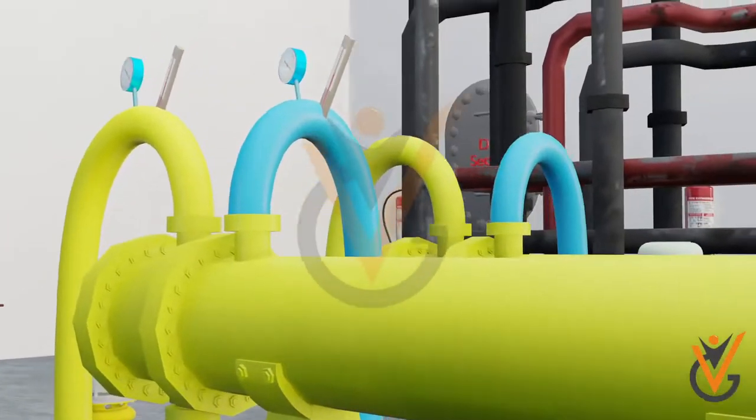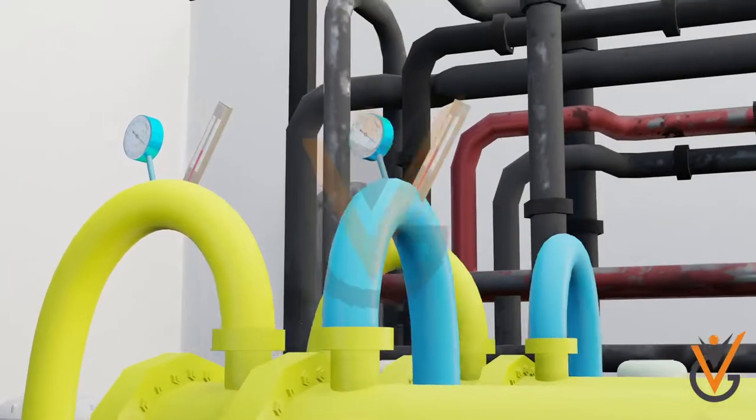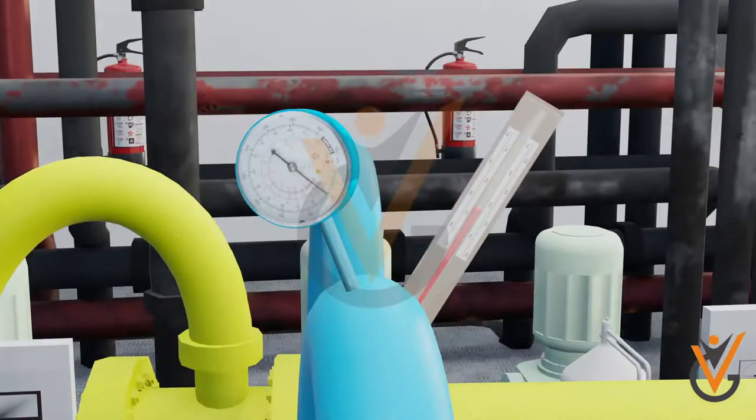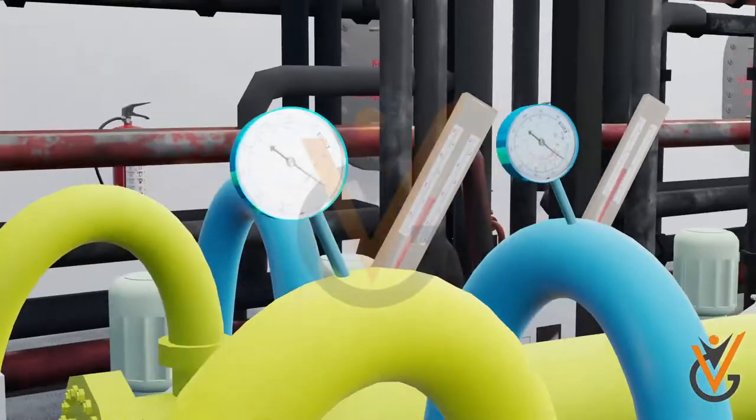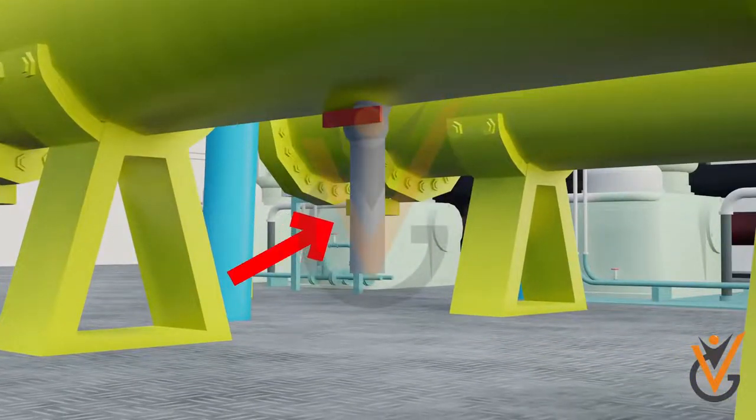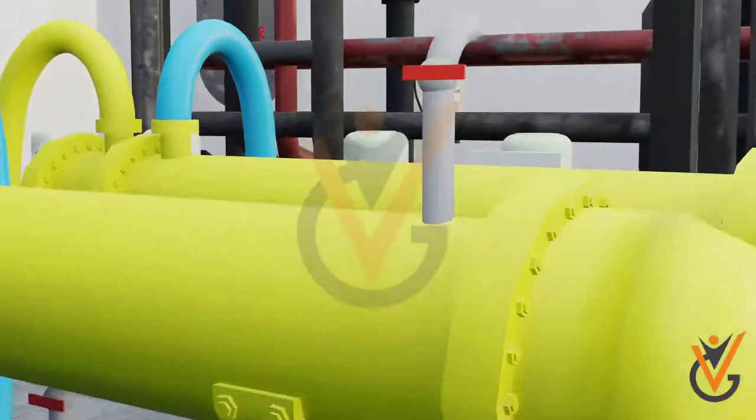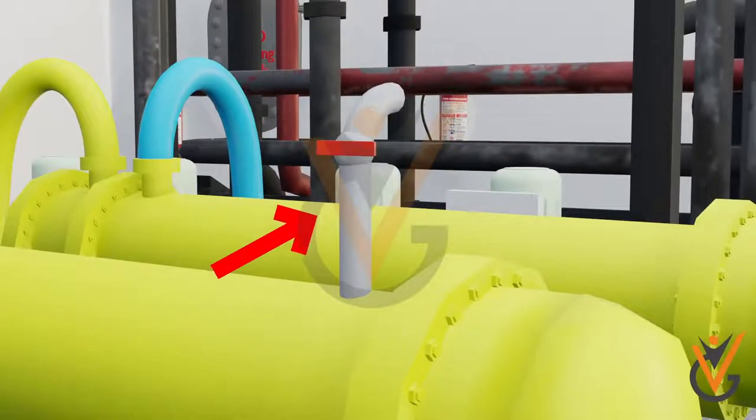Temperature and pressure gauges are fitted at the inlet and outlet flanges of both sea water and lube oil to monitor the operation of the heat exchanger. A drain valve is provided for both sea water and lube oil. An air vent valve is provided for venting out trapped air inside the shell of the heat exchanger.